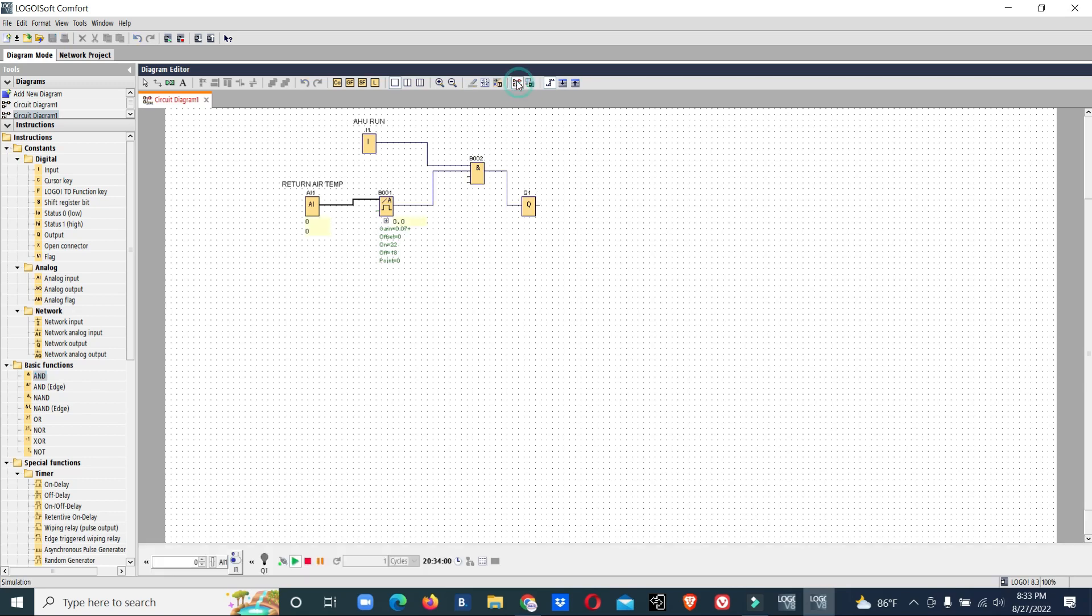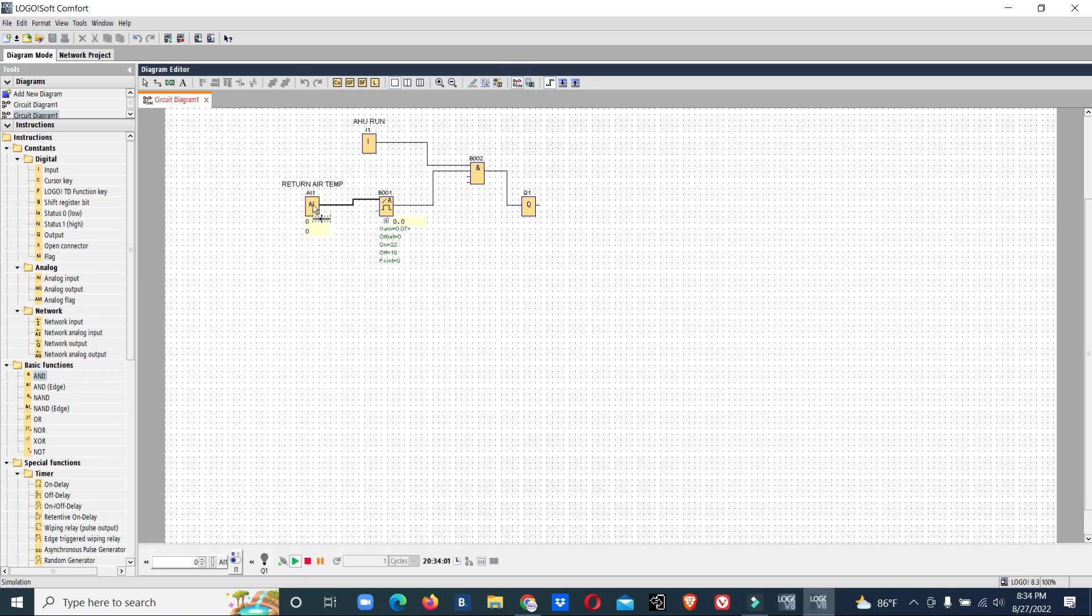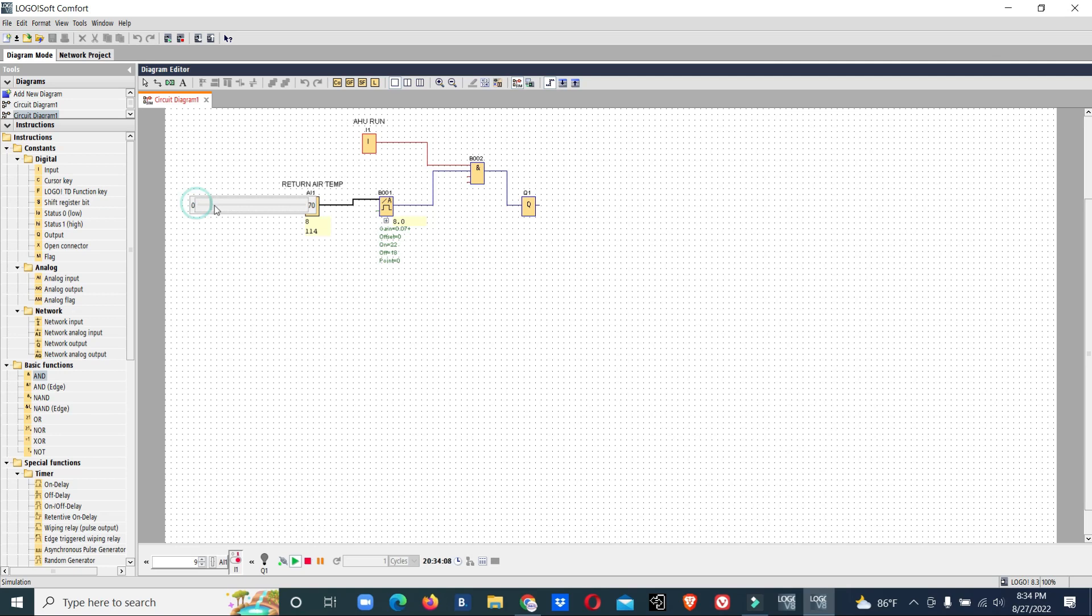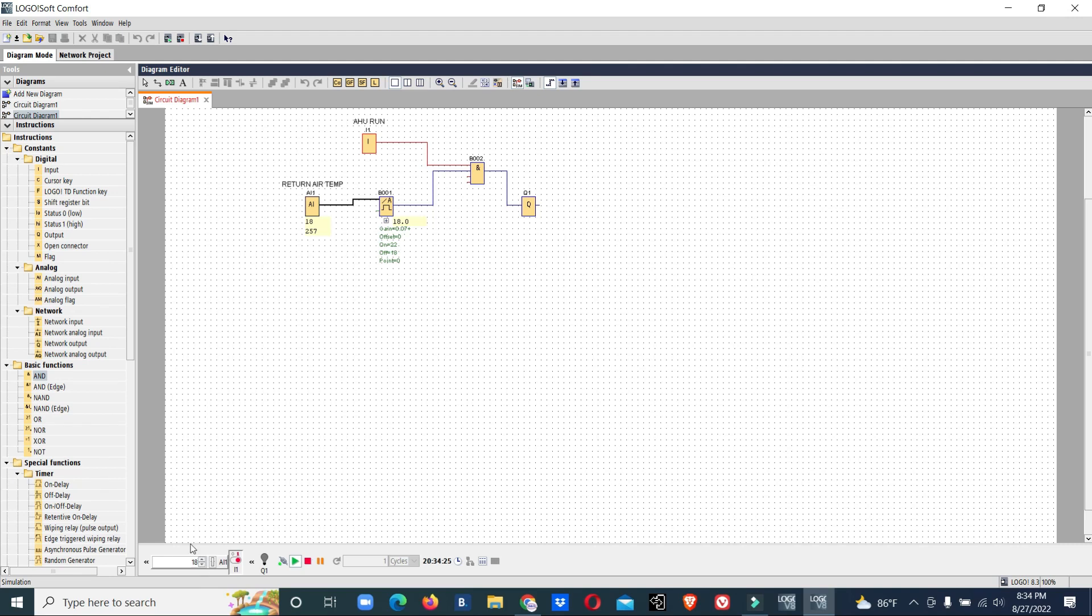Now we made the program. I will check it in simulation. Now AHU run command is received. We will increase our temperature. So run is 22. When it goes above 22, the AHU is started. So it will keep on running till cut-in temperature 18.